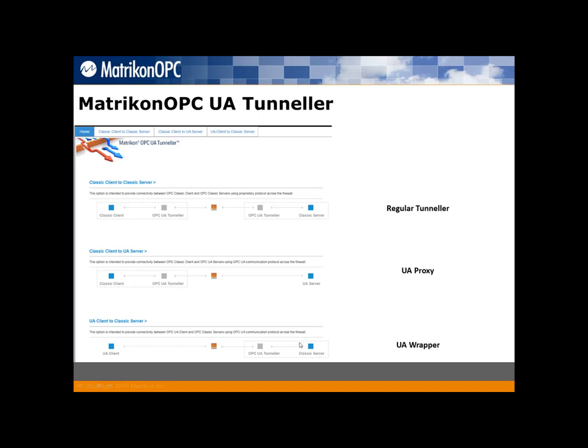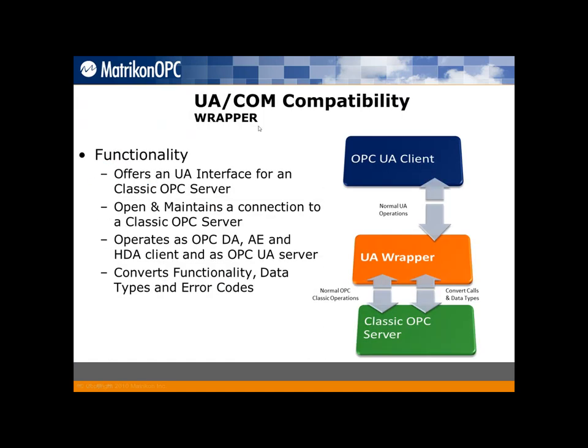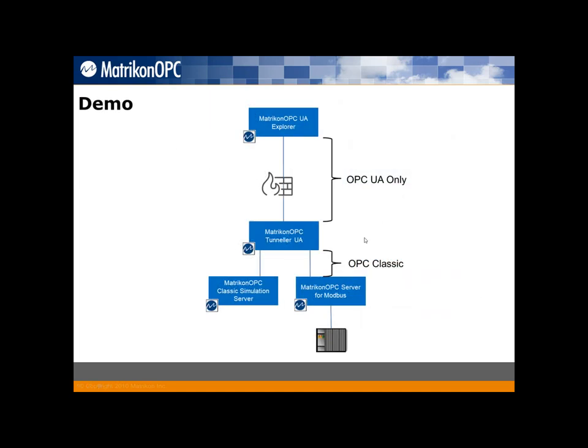The demo I'm going to show you is about the other functionality: the UA Wrapper. This converts an OPC classic server into an OPC UA server, so we can integrate those OPC classic servers we have in our company with OPC UA client applications. We just need to place a UA Tunneler together with the OPC classic servers. From the OPC UA client's point of view, it is connecting to one OPC UA server.